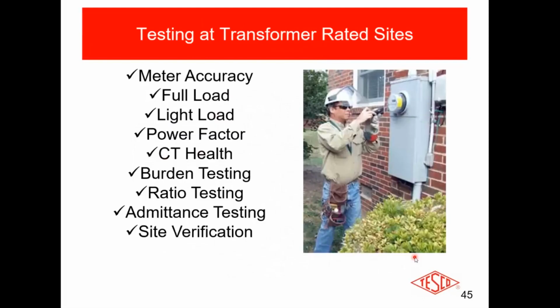All right. But now we're going to go back to our transformer rated sites. What do I got to check when I go out to my transformer rated site? What am I going to do? Well, I'm going to test my meter accuracy. Yep. I'm going to test it at full load, light load, and power factor. I'm going to check my CT health. What does that mean? Well, I'm going to do a burden check on it, and I'm going to do a ratio test on it. I can also do something called an admittance test.